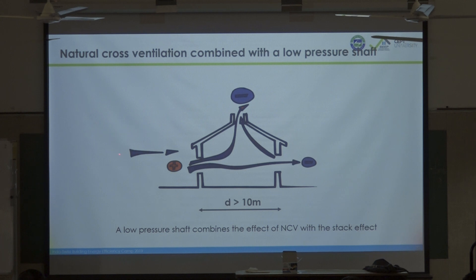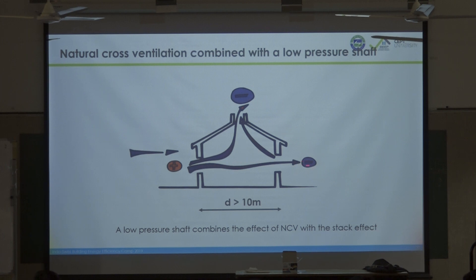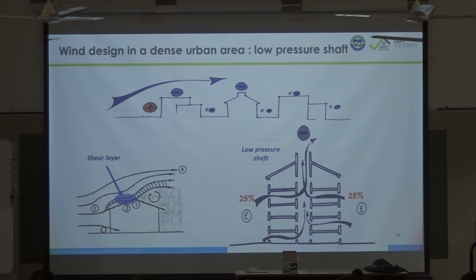With a low pressure shaft, if the wind comes from the left you have high pressure windward and low pressure leeward, but this shaft low pressure is even higher, multiplying the possibilities of air movement inside — from the windward facade and also from the leeward facade up to the top of the roof. This applies when the building length exceeds 10 meters, and can be used in dense urban areas where the building height must be above the surrounding buildings for the shaft to work.